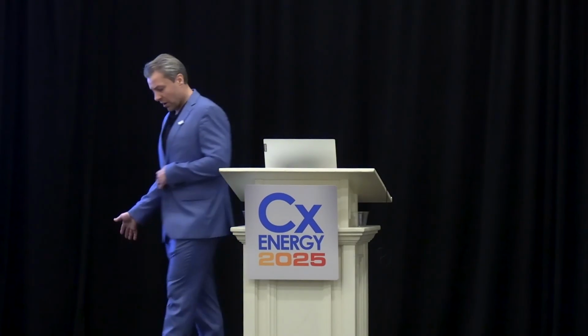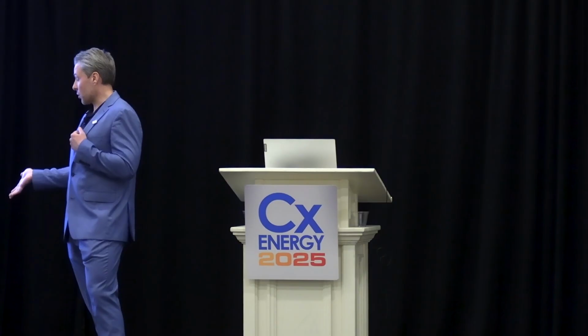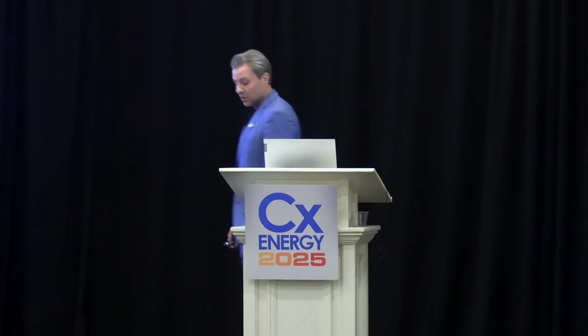What I was getting at with that - enterprise data centers are, as commissioning providers, the greatest opportunity for us to provide energy savings, because when those were built, enterprise data centers typically had a PUE around 4 or 5. I know when I was in the industry and we got to a PUE of like 3, we were like, oh my God, this is great. And now some data centers, the best one is like 1.07 or 1.08. So there's a lot of opportunities in the data center world for us to help owners get to their operational PUE and operational carbon emission goals.